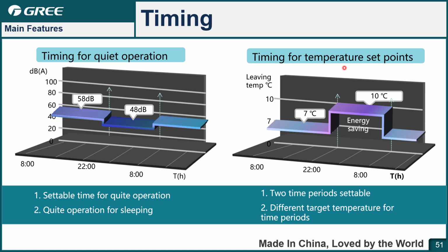And this is the timing for temperature set points. In daytime and nighttime, the load is different. In the daytime the load is high, such as a high cooling load, so you can set 7 degrees Celsius to get a higher output. However, at night you can set 10 degrees Celsius to reduce the power consumption. Yeah, you get some energy saving.